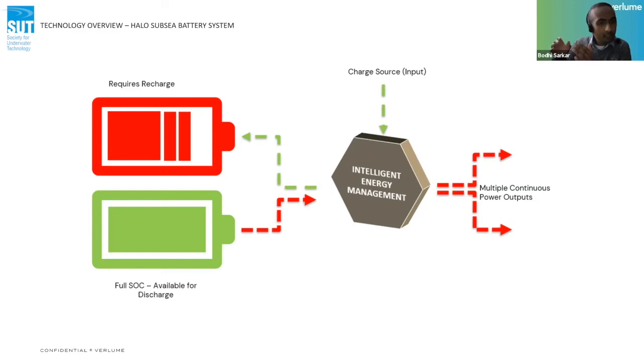So the energy coming in might be intermittent from the waves, and the various batteries are in a continual state of charge and discharge, but the system power output for the end application is constant and uninterrupted. So the simplistic illustration only addresses the power distribution, but the IEMS additionally offers a parent level protection for the entire system, addressing parameters such as overcurrent, over voltage, under voltage, over temperature, and under temperature. And the level of protection extends to environmental factors such as gas detection or moisture ingress, because ultimately we're packaging everything to be deployed in a harsh marine environment.